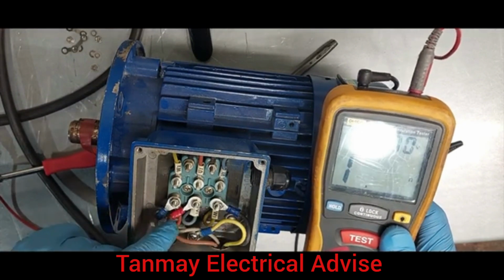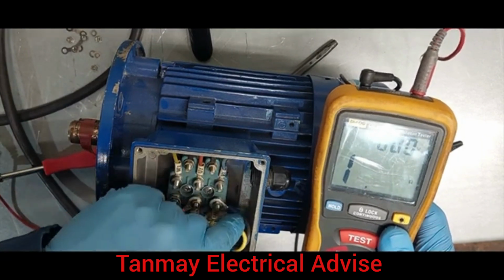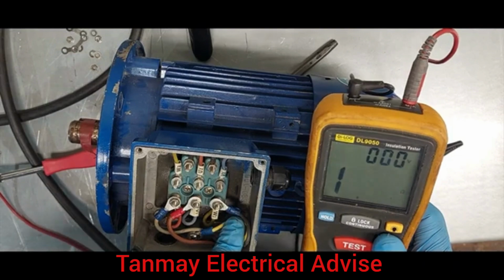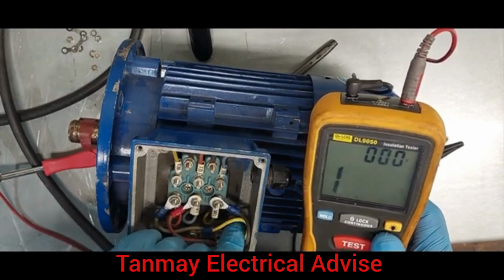So in this case, we're going to do the winding. We're not going to do the cable yet, but we'll also do that for the cable of the motor. But first of all, we're going to disconnect it and do it for the motor. And then we do it for the cable as well, to make sure that the insulation material can really withstand the voltage.